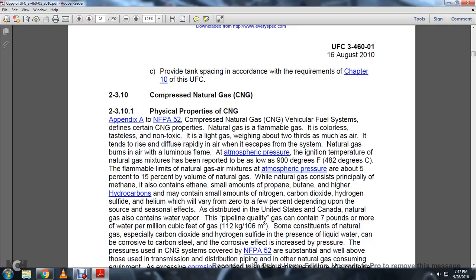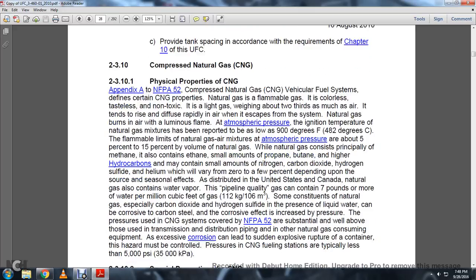Natural gas burns in air with a luminous flame, and at atmospheric pressure the ignition temperature of the natural gas mixture has been reported to be as low as 900 degrees Fahrenheit. Flammable limits of the natural gas mixture at atmospheric pressure are about 5% to 15% of the volume of natural gas. When the natural gas consists principally of methane, it also contains ethane and small amounts of propane, butane, and other hydrocarbons. It may contain small amounts of nitrogen, carbon dioxide, hydrogen sulfide, and helium, which vary from zero to a few percent depending on the source and seasonal effects, as distributed in the United States and Canada.